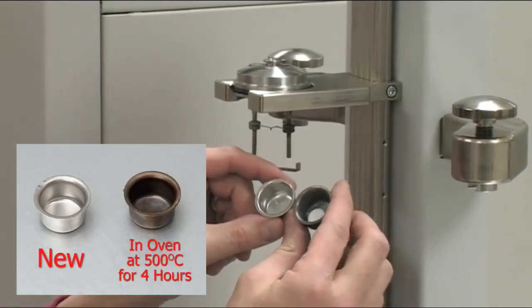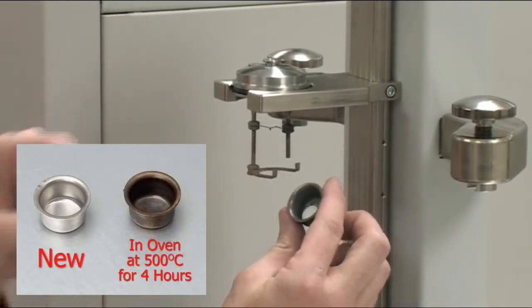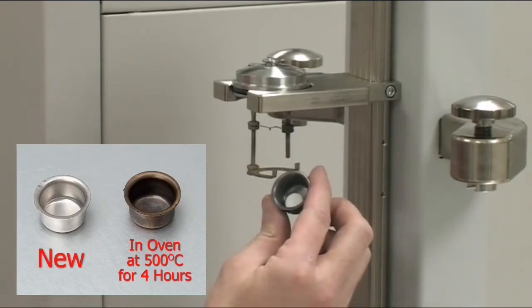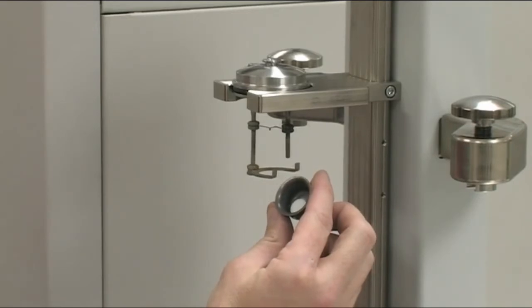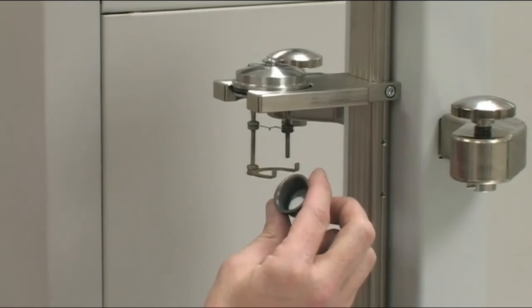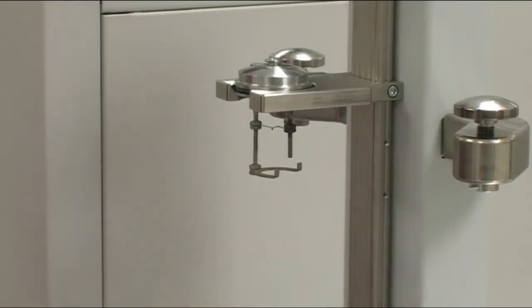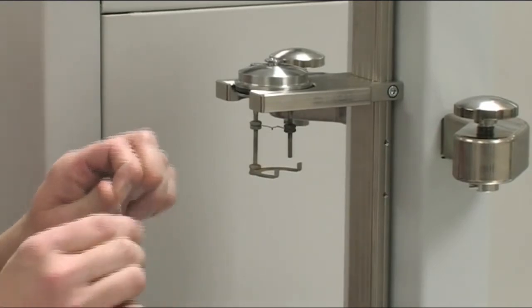When you prep the crucible, you have to take the new one and put it in the oven at 500 degrees C for 4 hours. After you run an analysis, you want to make sure the crucible is clean, and it may help to either put it in the oven again or just run a Bunsen burner flame into the crucible to make sure there's no leftover hydrocarbons. What we want to do next is attach the igniter string.